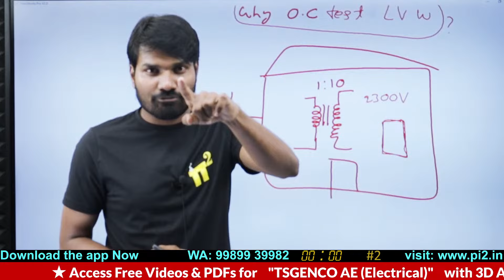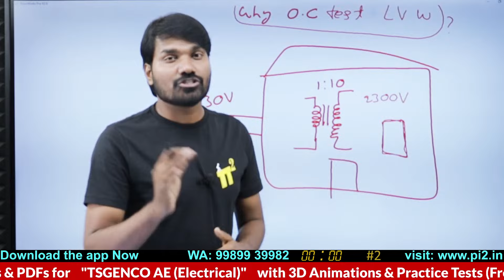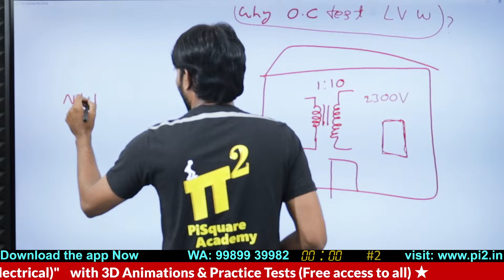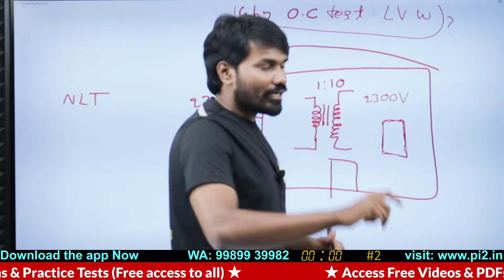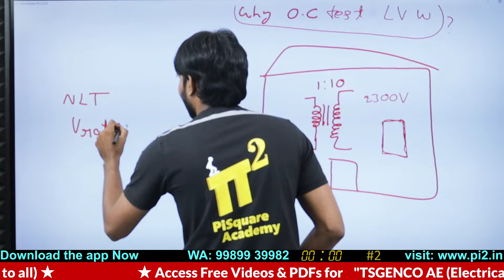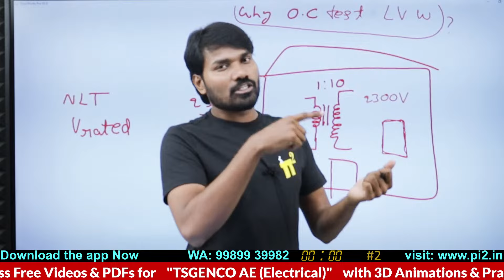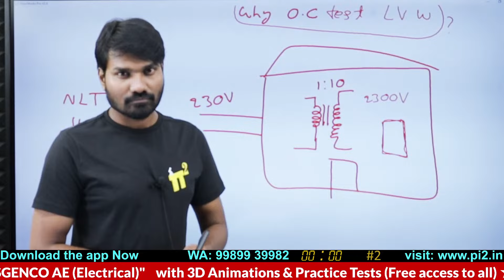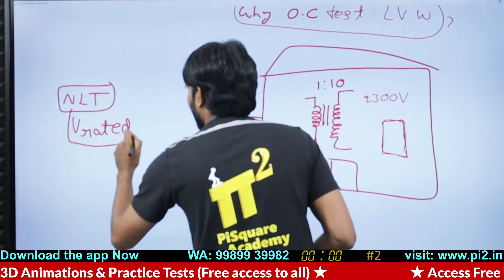Now suppose, guys, careful - suppose if I want to test this transformer, which test? No load test. I want to conduct a no load test on this transformer. We know for the no load test, I will have to give the rated voltage. Nowadays it's a digital meter, you connect the digital meter and the range will automatically adjust. Availability of meter is not a big aspect here. So I know no load test should be conducted at rated voltage.